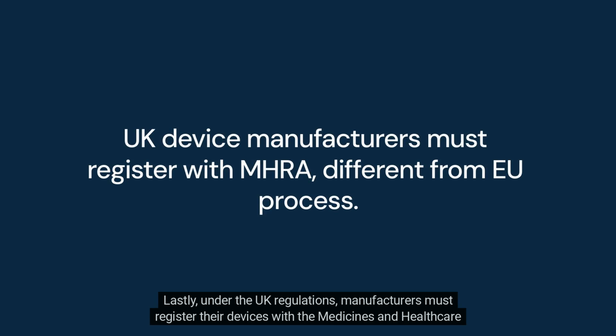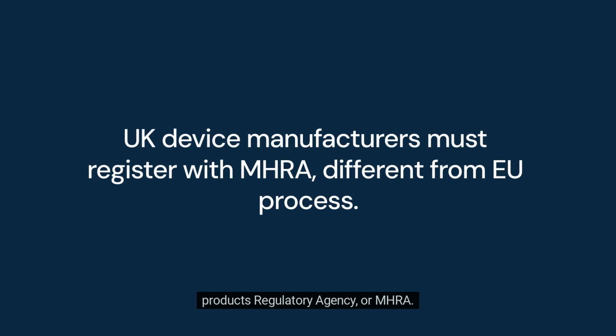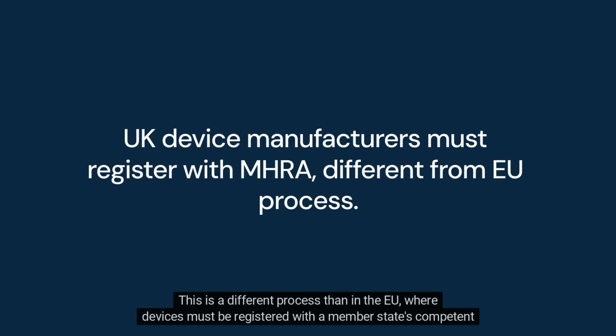Lastly, under the UK regulations, manufacturers must register their devices with the Medicines and Healthcare Products Regulatory Agency, or MHRA. This is a different process than in the EU, where devices must be registered with a member state's competent authority and on the EU EUDAMED system.